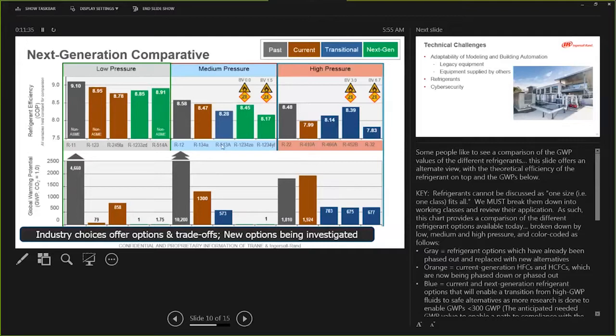Similarly, medium pressure refrigerants, and many are familiar with 134A, I think that we're on a good path for finding a long-term solution for medium pressure refrigerants. 134A has a global warming potential of about 1,300. As an interim solution, many suppliers of air conditioning equipment have introduced products with 513A. It has a very small efficiency hit compared to 134A, but it is near design compatible so that we can move to that refrigerant quickly. Unfortunately, even though it has a reduction in GWP of about 2/3 versus 134A, it's still not a good long-term refrigerant, so we consider it a transitional refrigerant in the industry at this point in time.